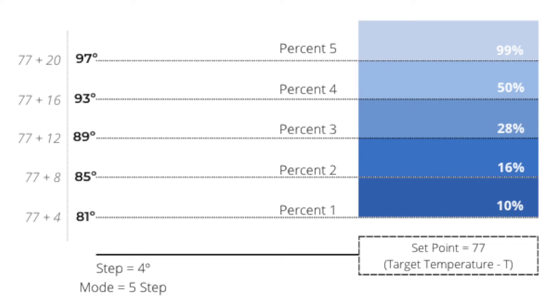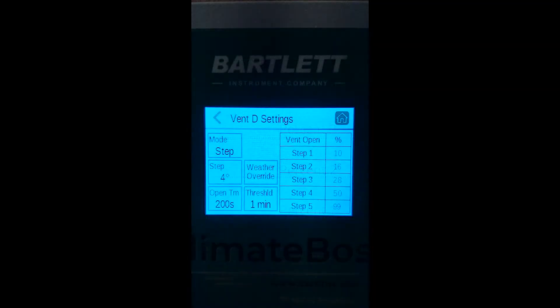Four more degrees will open to step three, 28 percent; four more to step four, or 50 percent; and four more and the vent will open completely to 99 percent. Five step mode is a good mode if you want to control each step percentage.